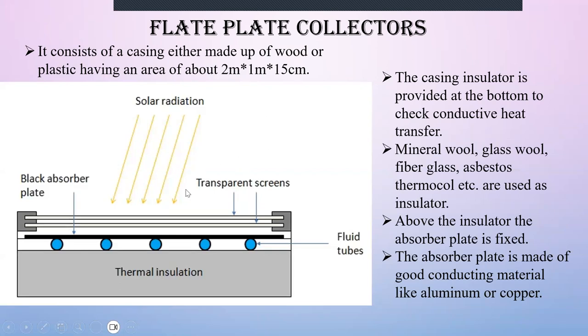A casing insulator is provided at the bottom to prevent conductive heat transfer. Mineral wool, glass wool, or fiberglass are used as insulators. Above this insulator, you can see the absorber plate that is fixed. This absorber plate is made up of copper or aluminum, which is a good conductor, and it is coated with black to increase its absorption property. This black coating is done by chemical treatment to allow maximum absorption of radiation and minimum emission.